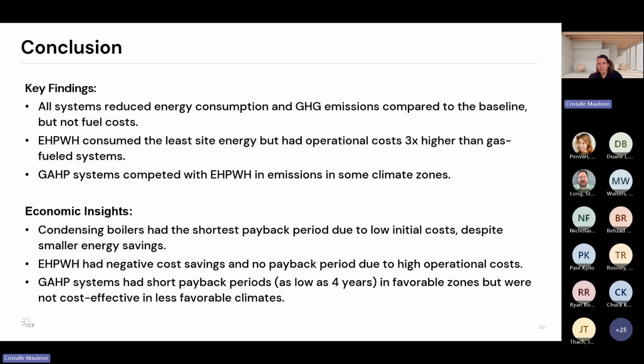So these are the key findings and economic insights from the study. Firstly, all systems, condensing boilers, electric heat pumps, and gas heat pumps, reduced energy use and greenhouse gas emissions compared to the baseline 84% efficient boiler. However, not all of the systems reduced the fuel costs. The electric heat pump water heater had the lowest site energy use, but its operating costs were about 3 times higher than the gas systems, making it the most expensive one to run.